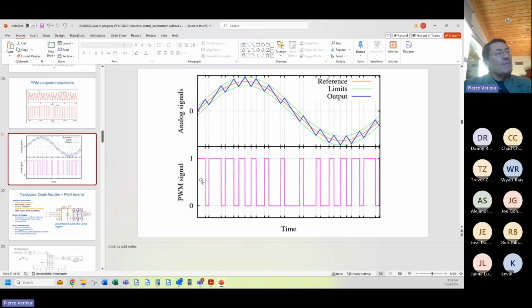There you have it. The problem with pulse width modulation is that every time you turn the transistor on, this pulse here, what's not shown is the voltage spike associated with turning the drive on. You go up and then come back down again. That voltage spike, the dVdt, change in voltage over change in time, is what harms the motor insulation. It's what you put filters on the output for, to protect the motor. The longer the motor lead lengths, the higher the voltage spike on every one of these pulses, every time you turn on. That is one of the downsides of using a constant voltage DC bus based variable frequency drive, what I refer to as the traditional variable frequency drives.